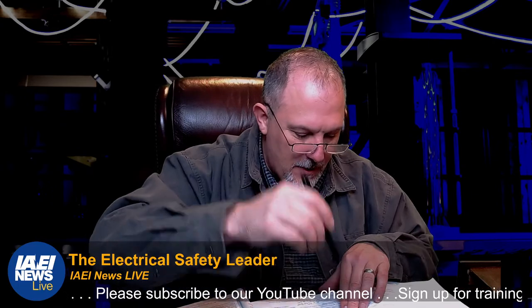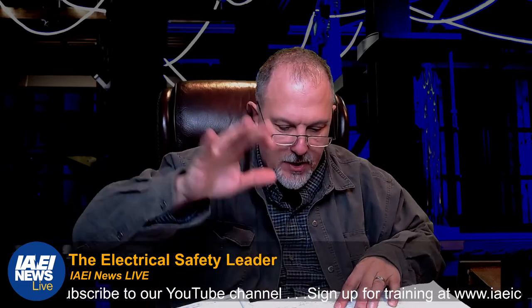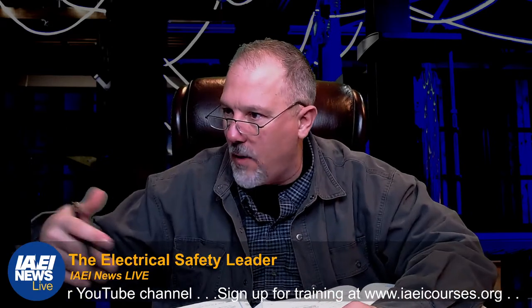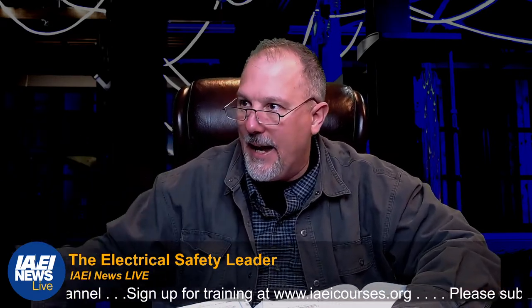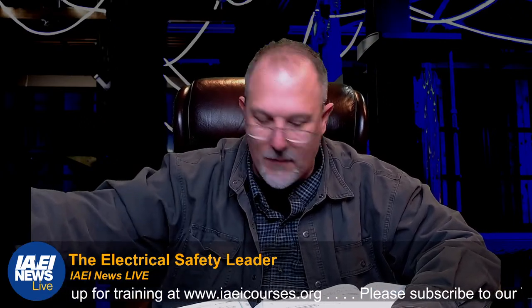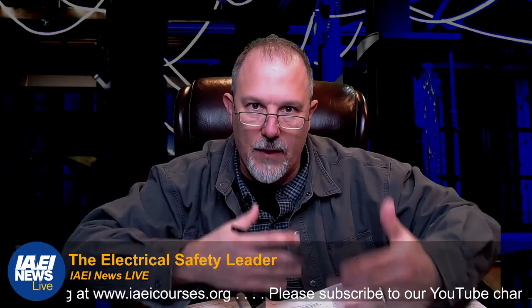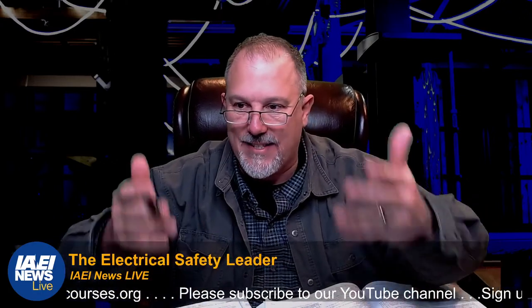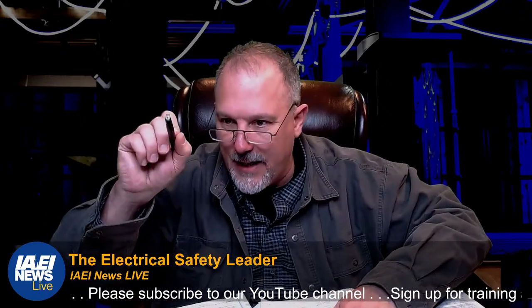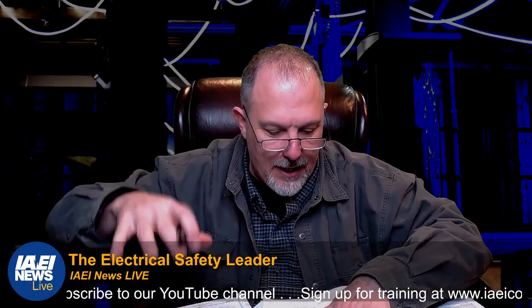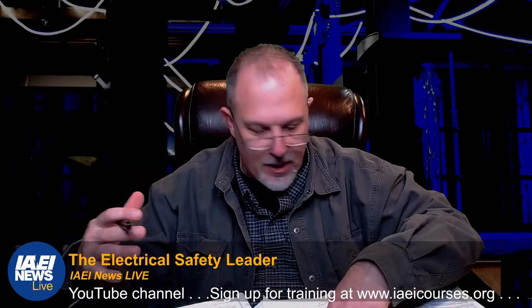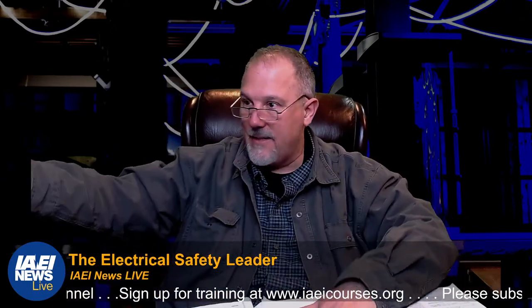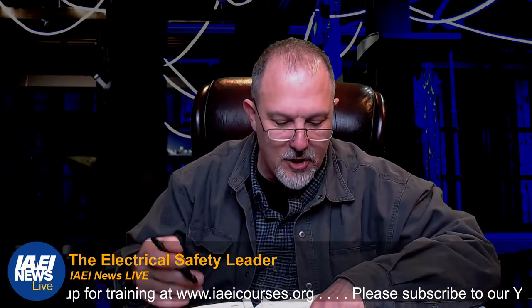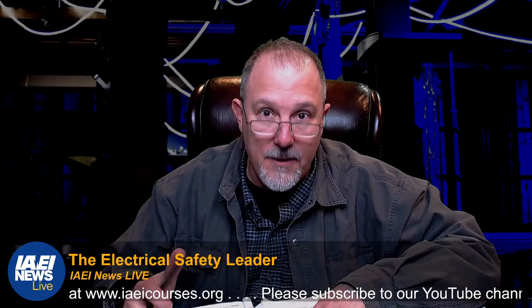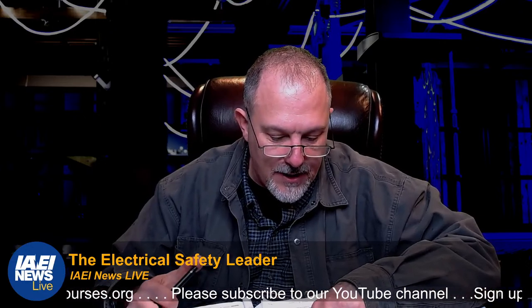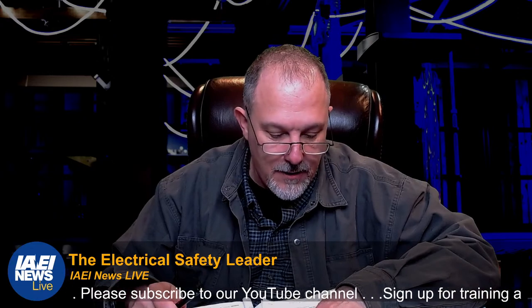All right, so there are system requirements, so there's commissioning, and I was going down the road of commissioning because I was in NFPA 855, and there's a chapter 6 for commissioning. And in Article 706 for energy storage systems, there is a section 706.7 for commissioning and maintenance. And to your point, Robert, NFPA 70B handles the maintenance side. The commissioning, it says, oh look at this, commissioning, chapter 6. It's referenced in the informational note to the first level subdivision A, commissioning. In 706.7, it tells us that upon installation, it has to be commissioned.